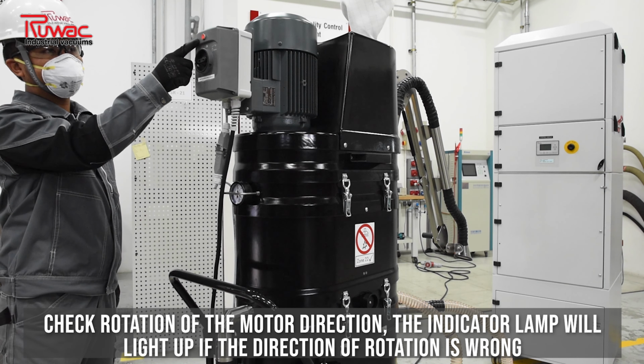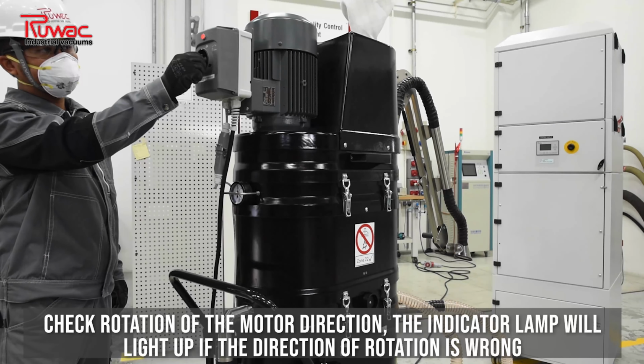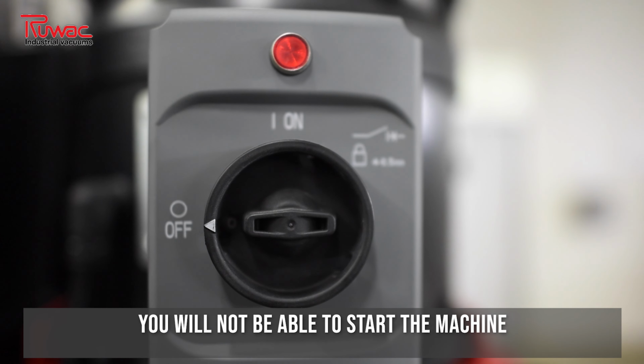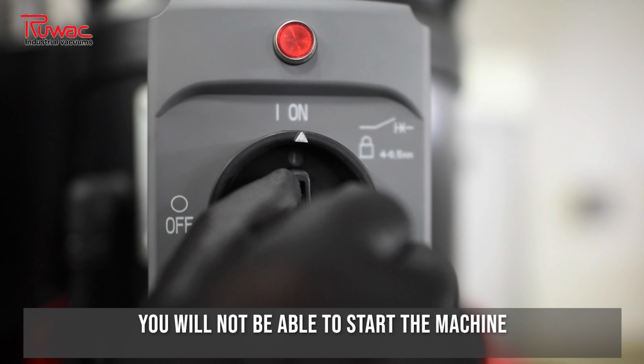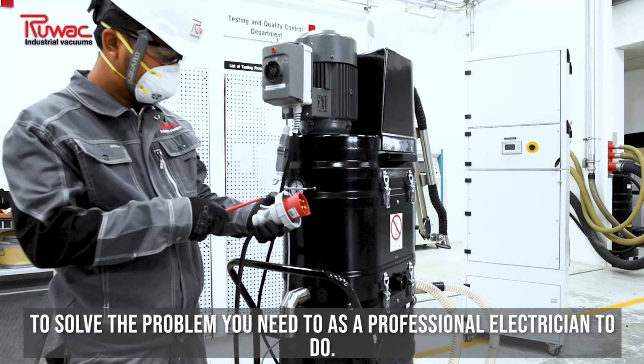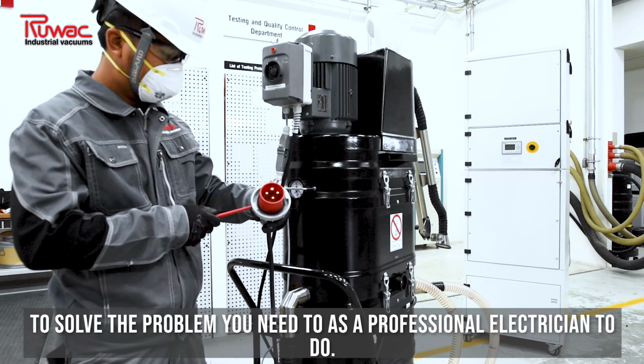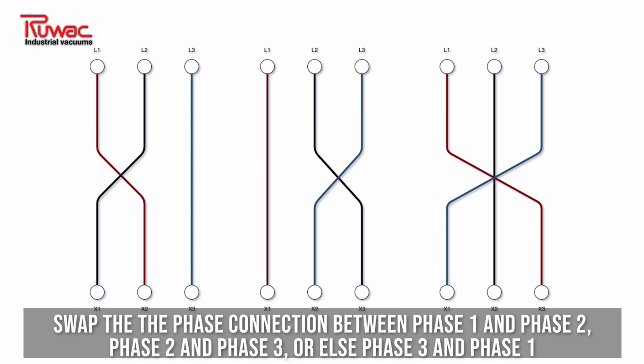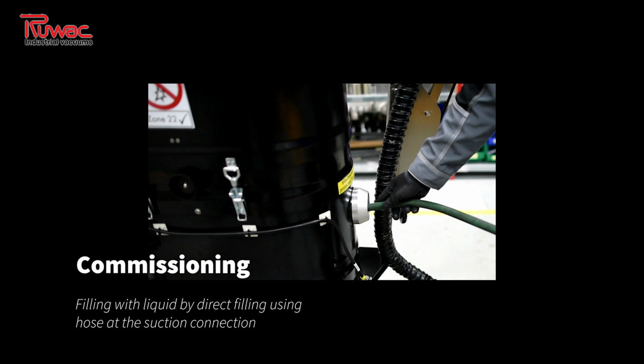Check rotation of the motor direction. The indicator lamp will light up. If the direction of rotation is wrong, you will not be able to start the machine. To solve the problem, you need to ask a professional electrician to swap the phase connection between phase 1 and phase 2, or phase 2 and phase 3, or else phase 3 and phase 1.